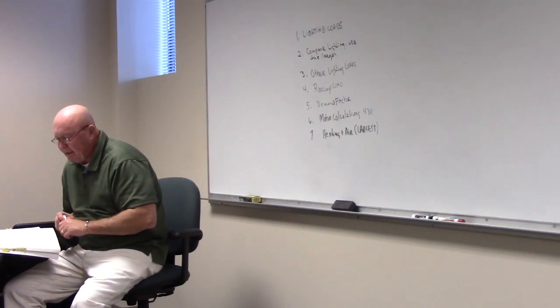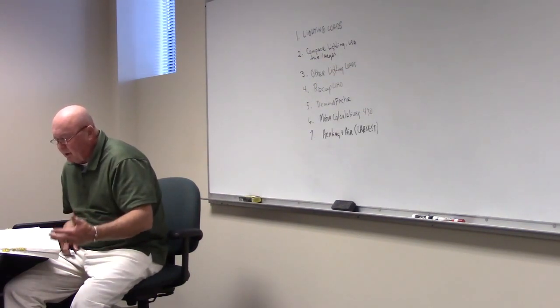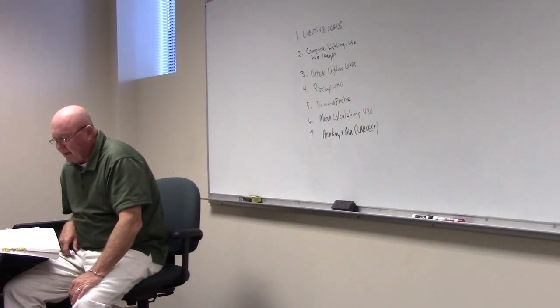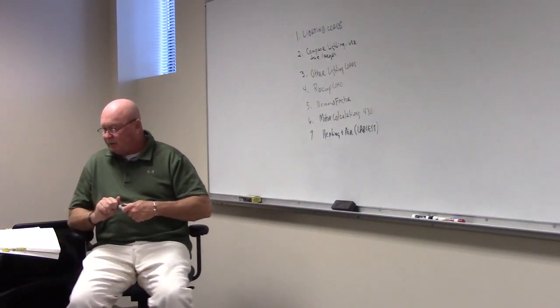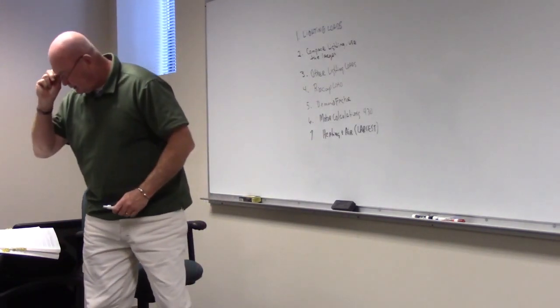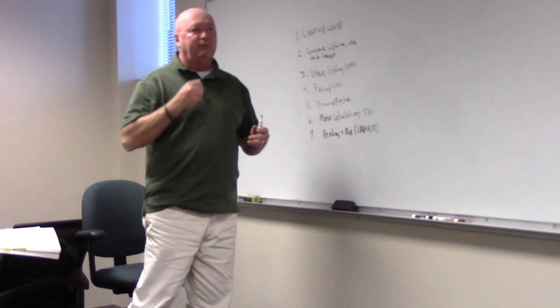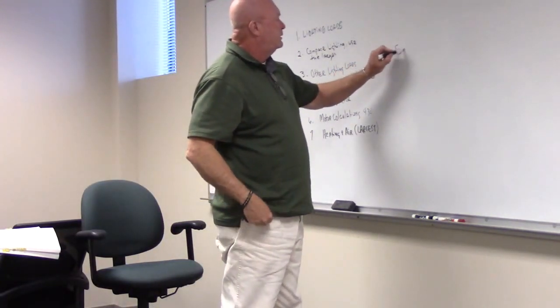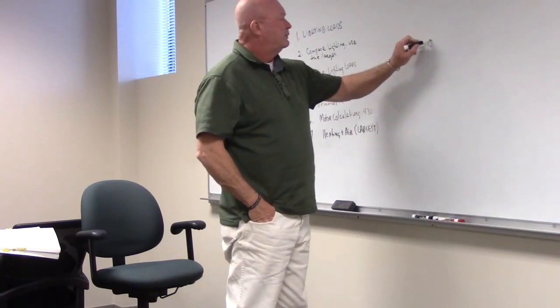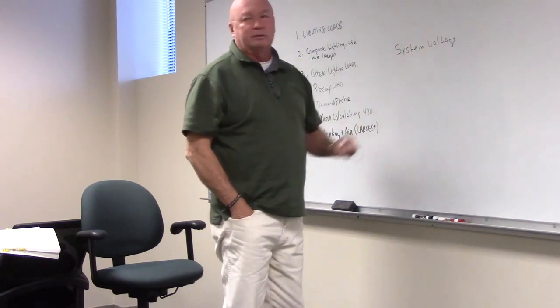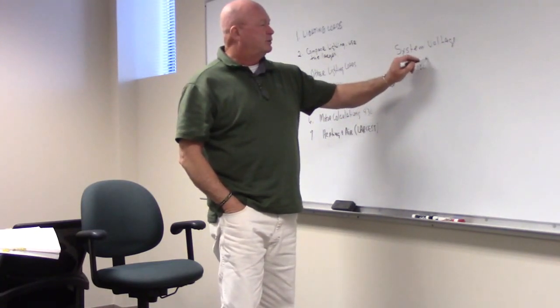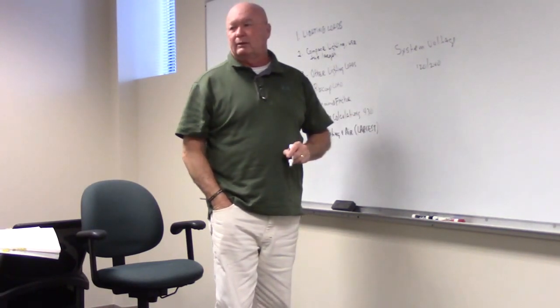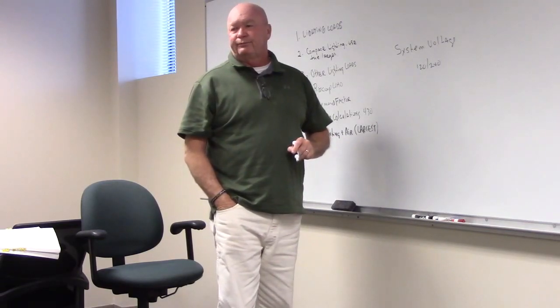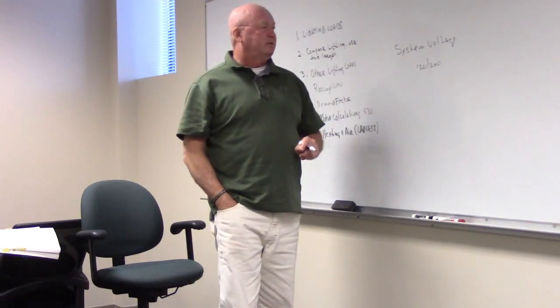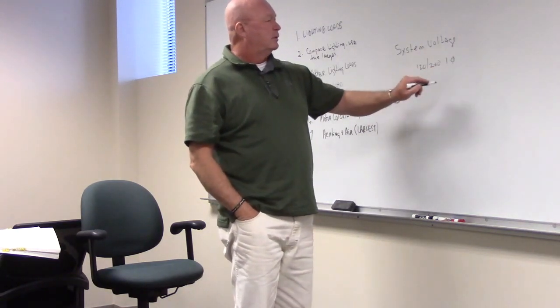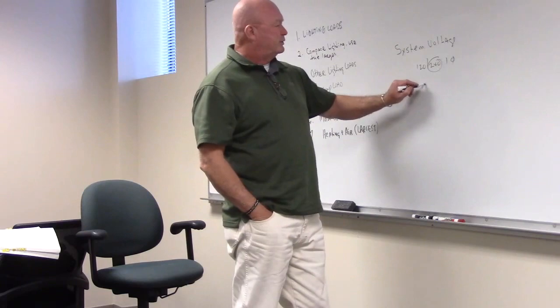All right, step number 8, if you look here, add all the loads. The resulting load in volt-amps is divided by the system voltage, and that's one thing I want to talk about too. Keyword: system voltage. Make sure that you're using the right one. On a single phase, if it's 120/240, what is your system voltage? 240.